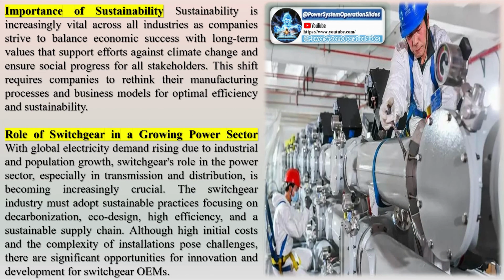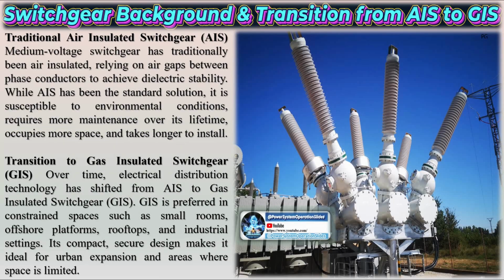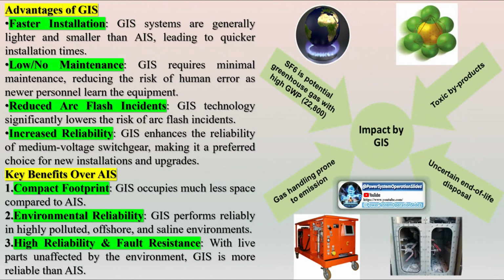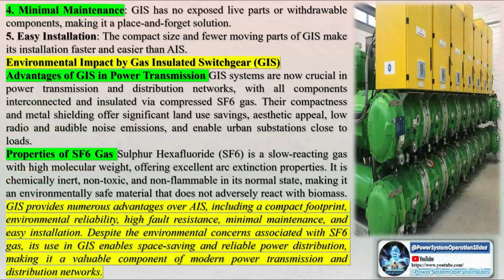GIS eliminates the need for air insulation, allowing it to be much smaller than air-insulated switchgear. This compactness is ideal for areas with limited space, such as indoor or urban settings. By enclosing components within modules, GIS prevents arc-causing incidents like vermin entry or conductive dust accumulation. This reduces arc flashes and increases overall safety. Additionally, SF6 is an excellent arc-quenching medium. GIS comes pre-assembled, making the installation process straightforward and quick. This leads to easier installations and shorter installation times.